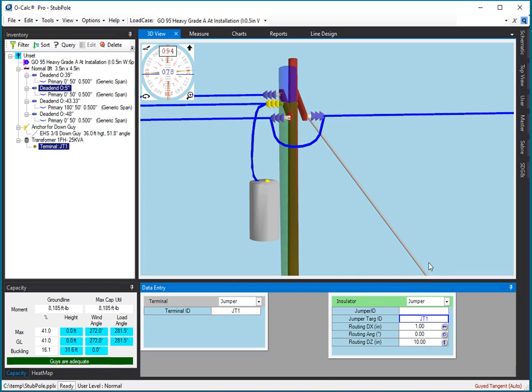And so now, I can actually add jumpers so that all of my electrical connectivity to switches, to transformers, between dead ends, between insulators, is correct, and the load is in fact added. It adds no tension load, but obviously it adds wind and weight loads.